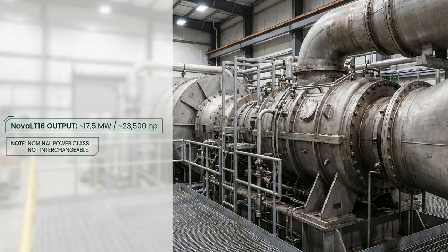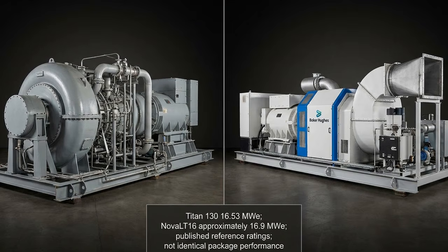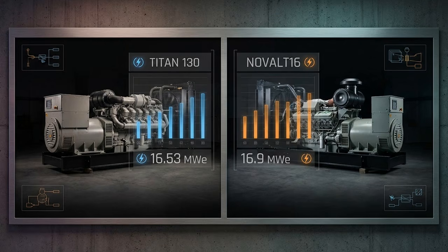The Baker Hughes Nova LT16 is a close nominal power class candidate. Published mechanical drive output is about 17.5 megawatts, or roughly 23,500 horsepower. That makes it comparable in headline rating, but not automatically interchangeable in package or compressor service. On a simple comparison, the Titan 130 is about 17.5 megawatts with approximately 36% mechanical drive efficiency, while the Nova LT16 is about 17.5 megawatts with approximately 37.5%. Treat this as a screening comparison, not a final project result. In power generation, published figures place the Titan 130 generator set around 16.53 megawatts electric and the Nova LT16 around 16.9 megawatts electric. Those values are close, but generator configuration, auxiliaries, controls, and site conditions still decide actual performance.